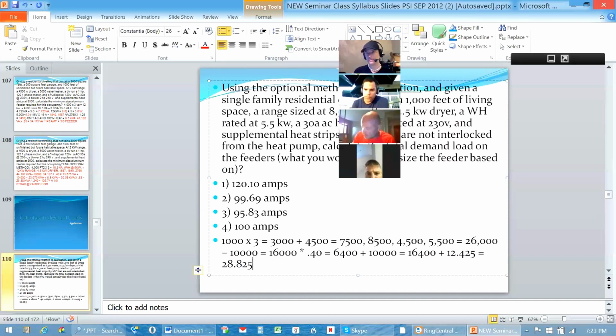I'm sorry, I'm trying to catch up. That 12,425 is what, if you look at section C3, I calculated for the heat pump. It came out at 100% of the heat pump, which is 6,900. Then I took 65% of the supplemental heat strips because they were not interlocked with the heat pump. When I add the 5,525 for the heat strips and the 6,900 for the heat pump, it gives me 12,425 altogether.